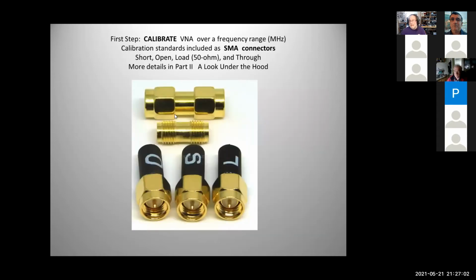So calibration, what's that all about? Well, at the end of the NanoVNA, these SMA ports come in a way pretty stupid. You have to teach it what's a 0 ohm load, what's an infinite load, and what's a 50 ohm load if you want to calibrate it to 50 ohm. So it's called a SOL.